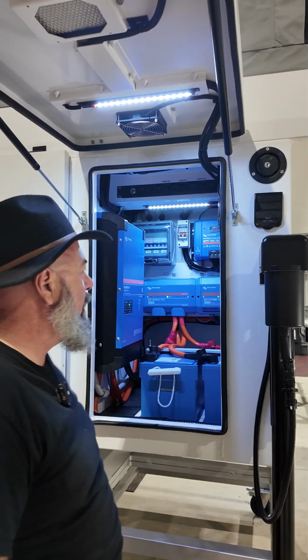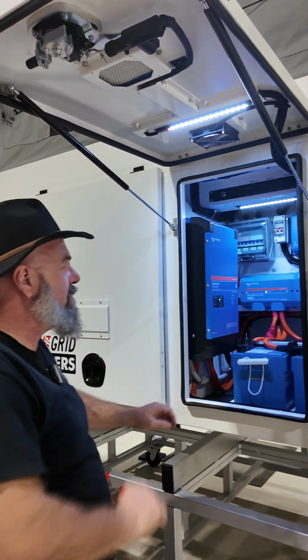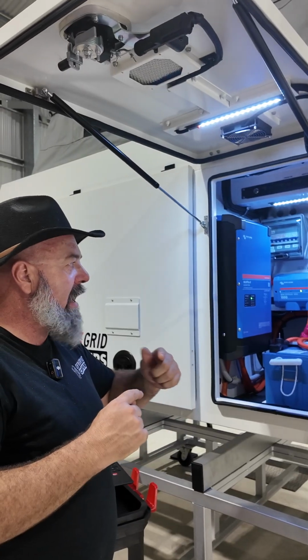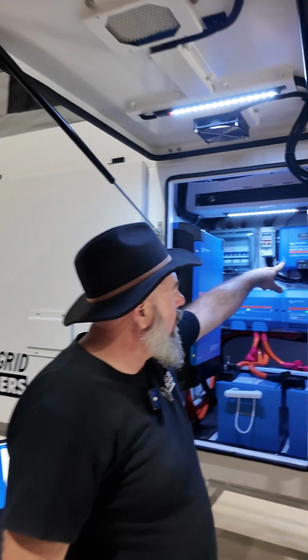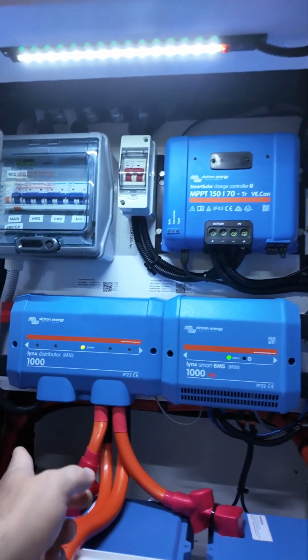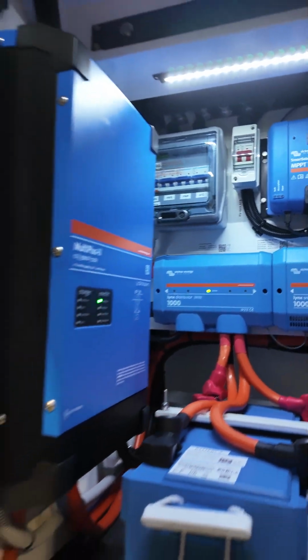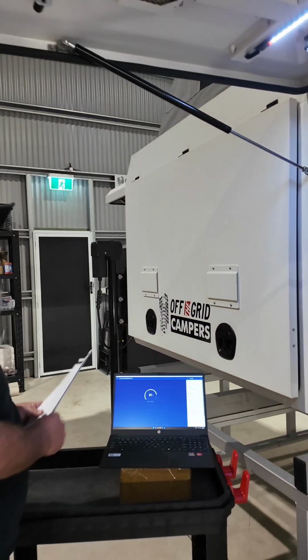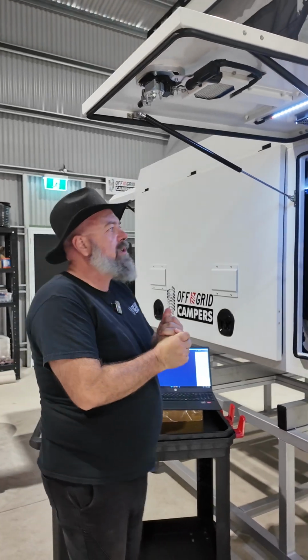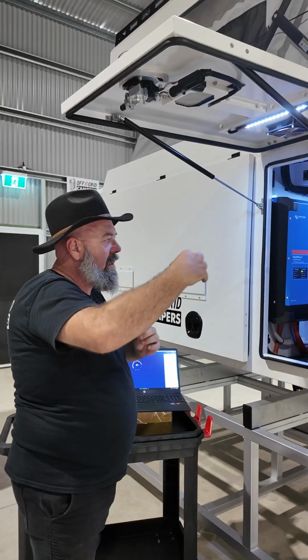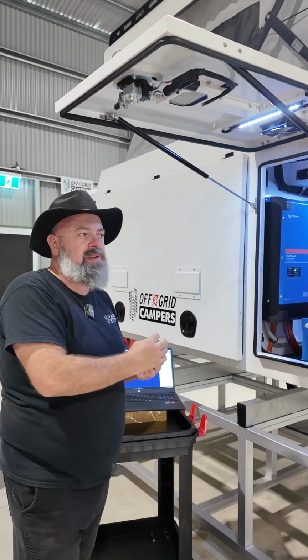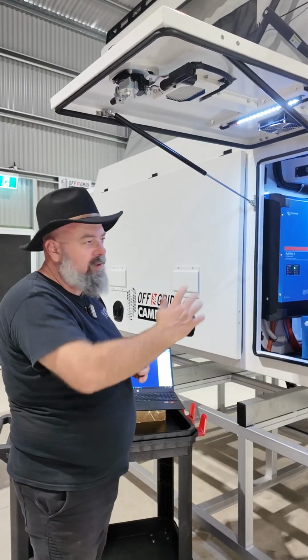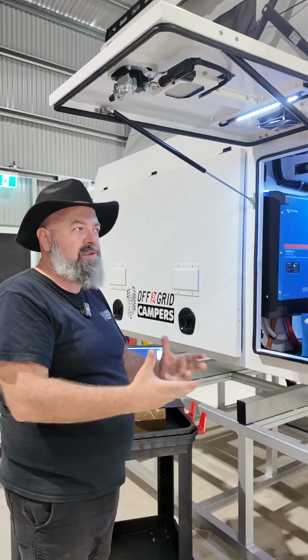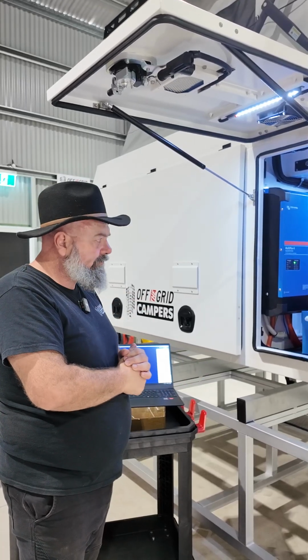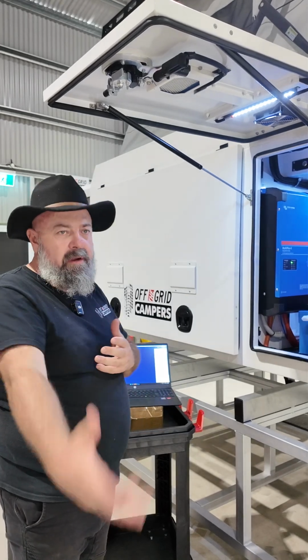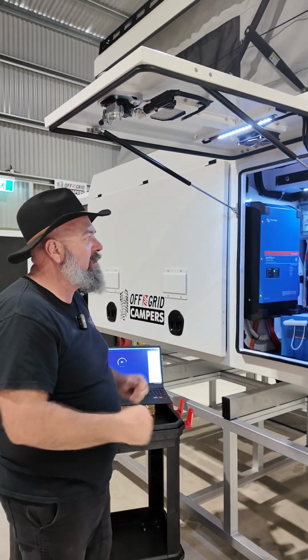Your BMS, to a large extent, is the brain of this system. It automatically communicates the settings to other devices like your solar charger and your DC charger. They do get programmed individually, but the BMS can also communicate with them to make sure the current being pushed into the batteries is what they need, increasing or decreasing current based on their state of charge. That stops the state of charge getting too low or overcharging - that's what the BMS does, communicating with everything feeding into it.